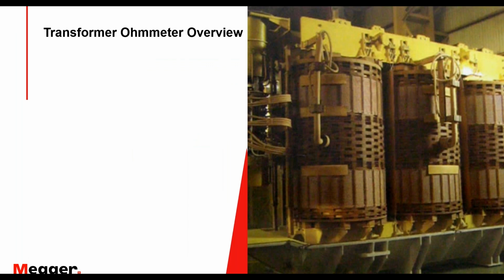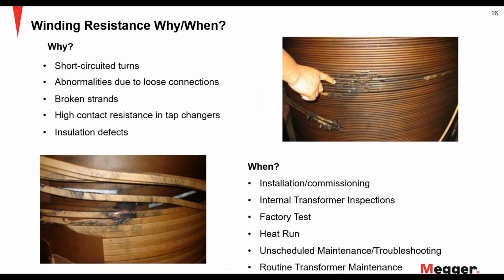Now we know how to test insulation resistance. We know theory about it. So let's jump a little bit to transformer ohm meter overview. That's basically your winding resistance. When do you do it? Why do you do it? What does it tell you? So you can detect short circuited turns in the transformer itself, any anomalies due to loose connections in the transformer, broken strands, high contact resistance in tap changers. So it's all integrated in the winding resistance test, and from those readings, you can determine any kind of insulation defects in the winding.